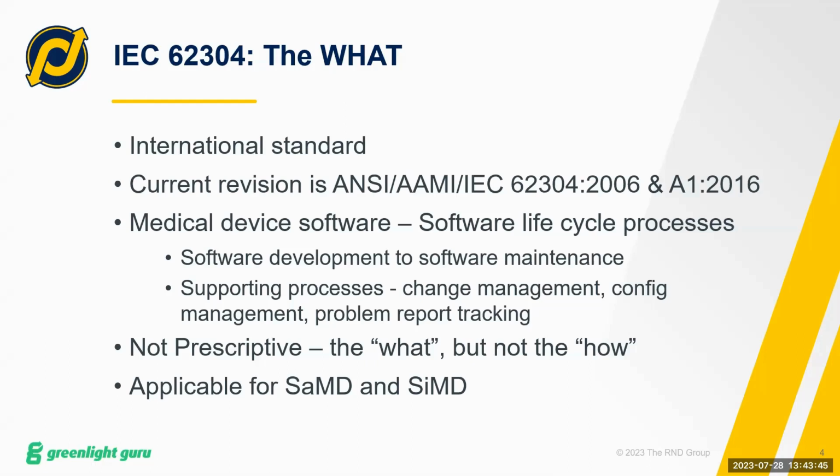It originated with IEC. That's the originator of the standard. The title of it is called Medical Device Software Lifecycle Processes. It contains processes and requirements that cover software development all the way through software maintenance. It also gives you supporting processes like change management, configuration management, and problem report management and tracking.